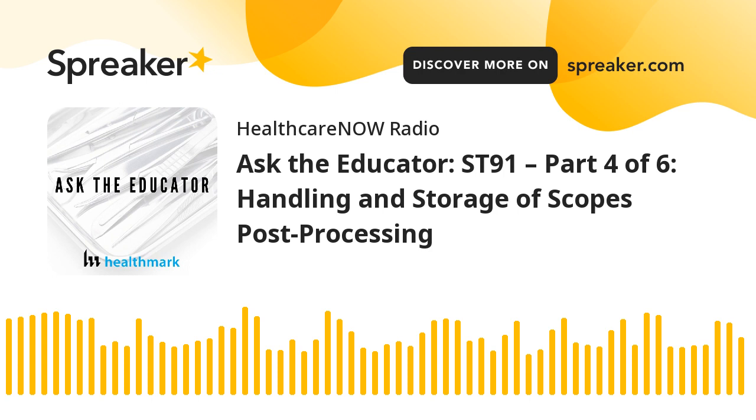The second thing to touch on: after figuring out what type of air we need, it can be common for folks to use the same endoscope five, six, or seven times a day. The question that comes up is, is there really time in between to perform this 10-minute drying step? A lot of times people take a scope out of an AER and it goes right into a procedure room. There were even places in health systems that questioned: if it's going right to another room, what's the issue with drying—do we really need to do that?